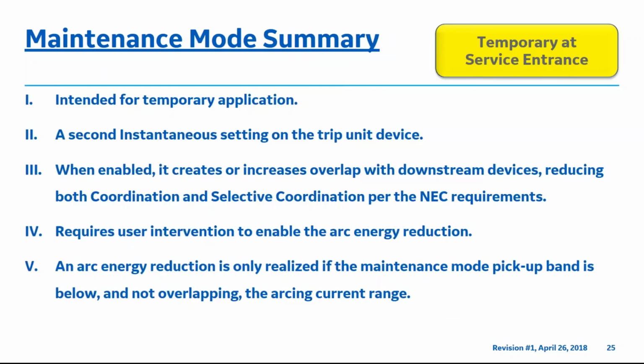The first summary point in the maintenance mode, which again is highlighted in yellow in the upper right-hand corner, meets the requirements per the 2017 NEC Article 240.67(B)(2). The first line item is that it is intended for temporary application. Second, it is an instantaneous setting on the trip unit device. Line item number 3, when enabled, it creates or increases the overlap with downstream devices, reducing both coordination and selective coordination per the NEC requirements. Line item number 4, it requires user intervention to enable the arc energy reduction. And finally, line item number 5, an arc energy reduction is only realized if the maintenance mode pickup band is below or to the left, which refers to the purple vertical line, and not overlapping the arcing current range, which is the red transparent line.